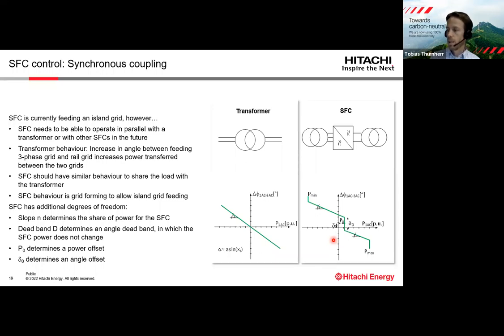Or we can set the characteristic in a way that the SFC supplies power towards the catenary, towards the railway line, but as soon as power is being or wants to be fed back towards the three-phase grid, the SFC doesn't react until the angle crosses a certain threshold. So there is quite some flexibility in setting the SFC behavior with this characteristic. And depending on how the characteristic is set, this is indicated with 3 examples here. The transformer and the SFC share the load.